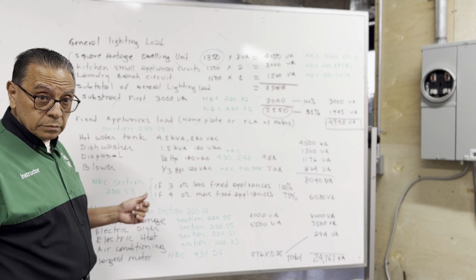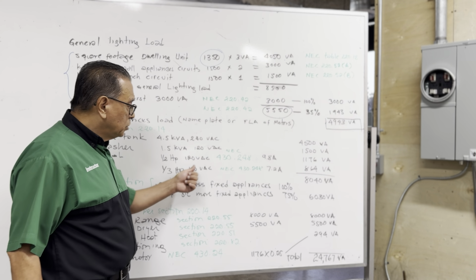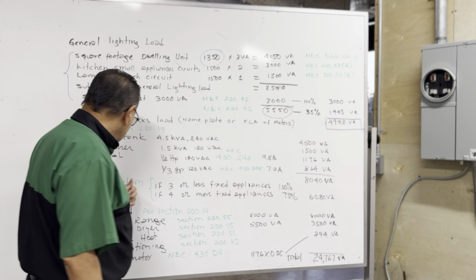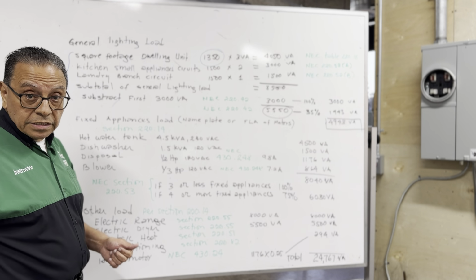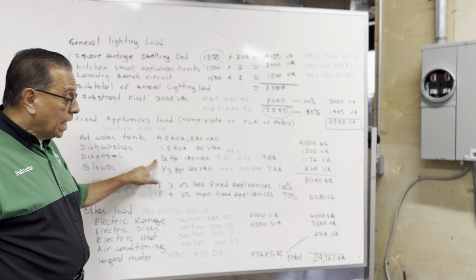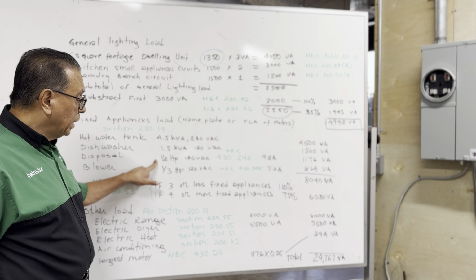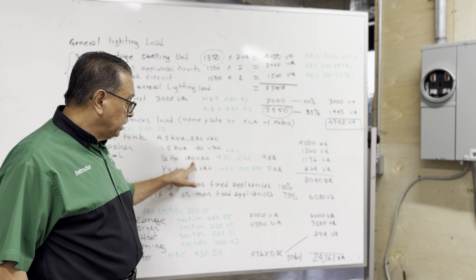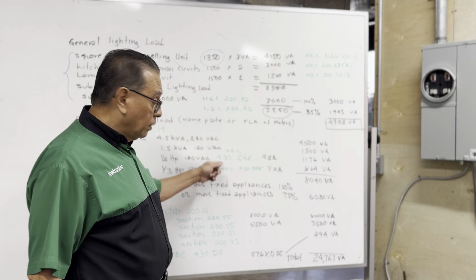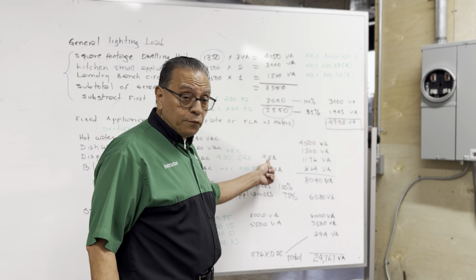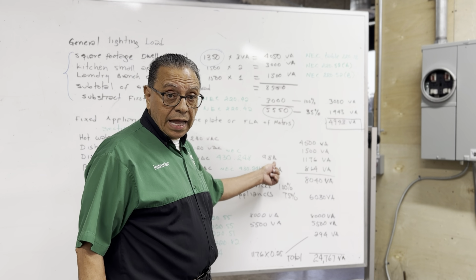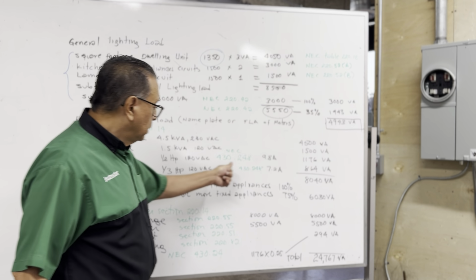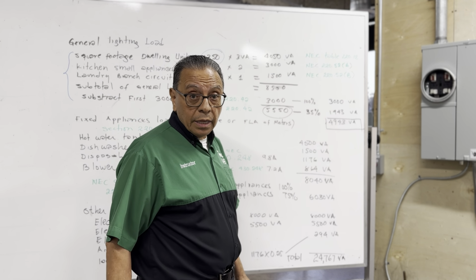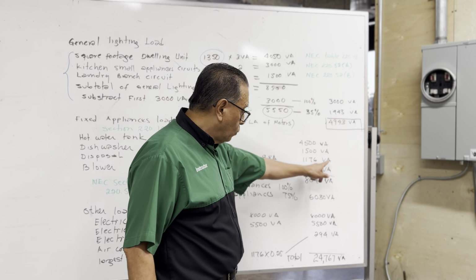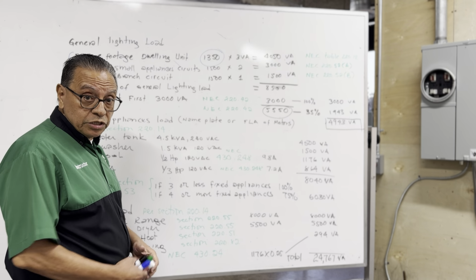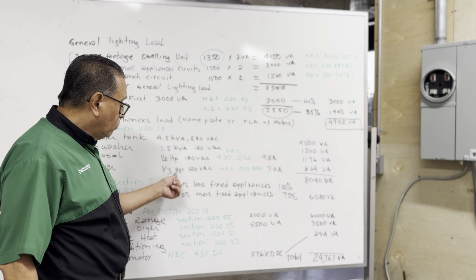The dishwasher, 1.5 kilovolt ampere, which is 1,500 volt ampere. And the garbage disposal is an electrical motor, a half horsepower electrical motor working with 120 volt AC. According to table 430.248, the full load capacity is 9.8 amps. If I multiply 120 volts times 9.8, I get a total of 1,176 volt ampere.